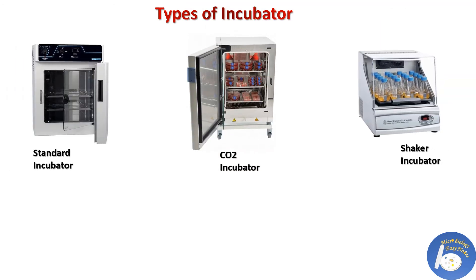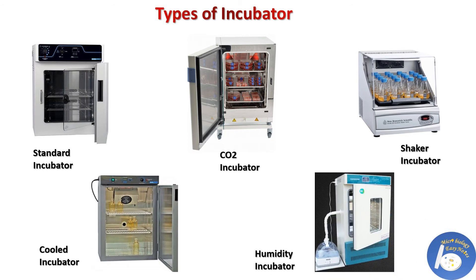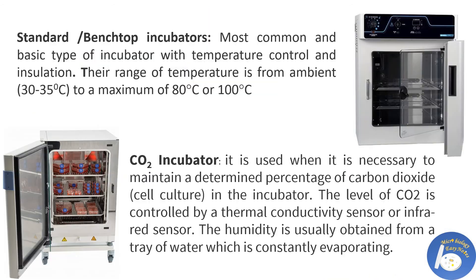There are many kinds of incubators: standard incubator, CO2 incubator, shaker incubator, cold incubator, and humidity incubator. The first is the standard or bench-top incubator, which is the most common and basic type with temperature control and insulation. These incubators can be gravity or fan-assisted convection, and their temperature range is from ambient (30–35°C) to a maximum of 80–100°C.